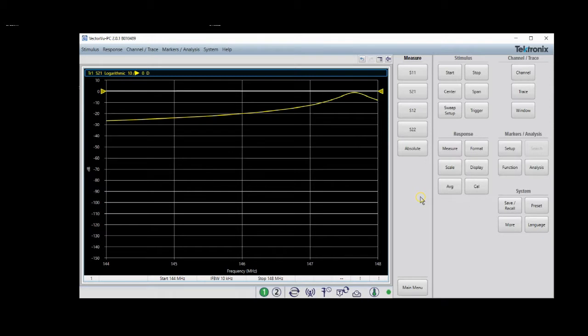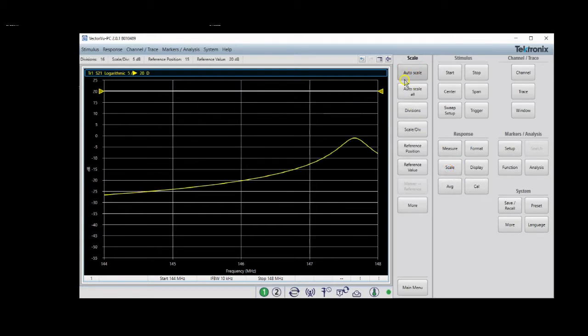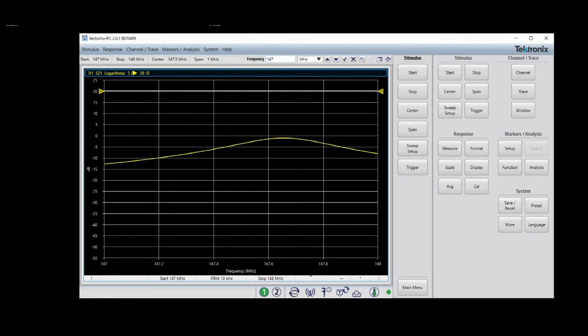There we go. Okay. It's just this little bump here. So let's go to scale, and we're going to auto scale so that we can see things better. And even there, we could probably make that better, but we want to zoom in here. We can see our little peak is right here. We want to zoom in to this point here. So we're going to change our start frequency. Remember, it's okay to calibrate wider and go narrower. You lose some accuracy by doing that, but for the sake of what we're doing, the loss of accuracy is going to be minimal. So I'm just going to change the start frequency to 147 megahertz. And it looks like a little bump again. Let's re-auto scale. There we go.